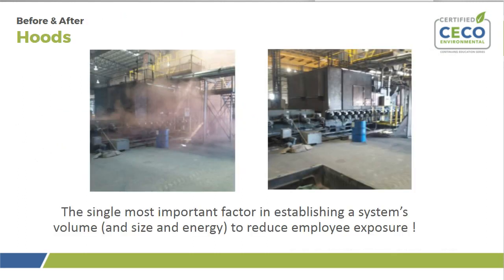A well-designed hood will reduce, if not eliminate, employee exposure at the hazardous contaminant source. And hoods are the single most important factor in establishing a ventilation system's volume and size and energy to reduce employee exposure. Thank you, Vern. Those pictures were quite the difference between the before and after. Quite interesting to look at.